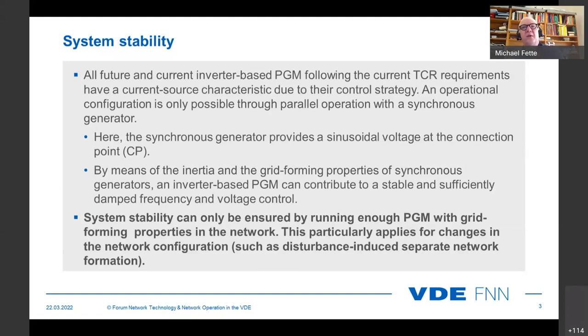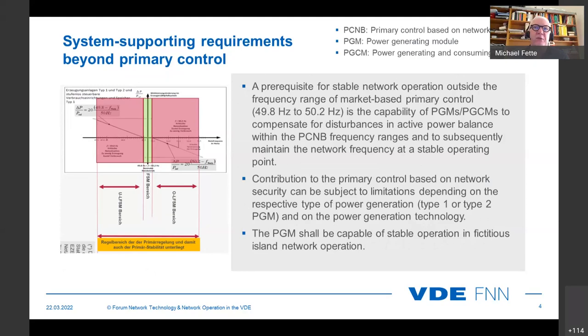The first prerequisite for stable network operation outside the frequency range of market-based primary control is the capability to compensate for disturbances in the active power balance within the network frequency ranges and to subsequently maintain the network frequency at a stable operating point. The contribution to primary control based on network security can be subject to limitations depending on the respective type of power generation, type 1 or type 2 PGMs, and on the power generation technology. And the PGM shall be capable of stable operation in fictitious island network operation. The name fictitious island network operation will be very important in the next topic we have to discuss. So we are looking at the following.